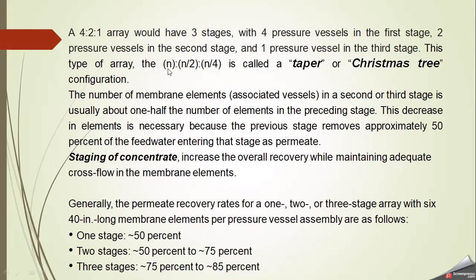This type of array can be generalized as n, n/2, n/4 where n is a whole number. This arrangement is called a taper or Christmas tree configuration. The number of membrane elements in a second or third stage is usually about one half the number of elements in the preceding stage. This decrease is necessary because the previous stage removes approximately 50% of the feed water as permeate, so only half the water enters the next stage. Reducing pressure vessels maintains the required cross-flow pressure, and this staging of concentrate increases overall recovery while maintaining adequate cross-flow in the membrane elements.